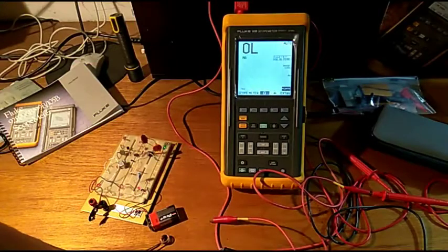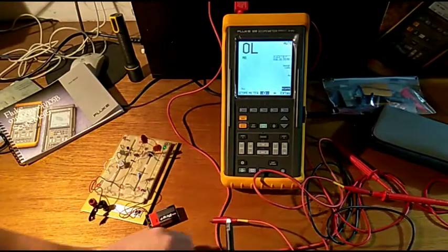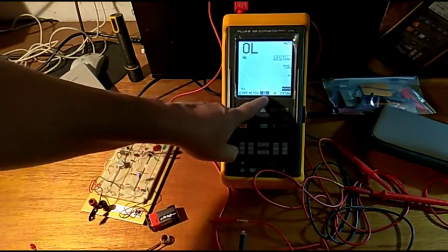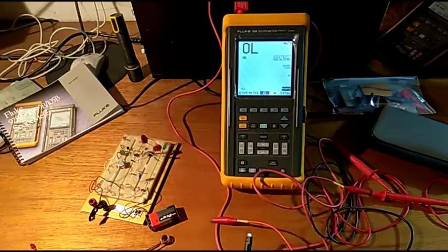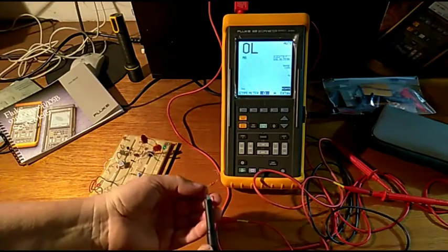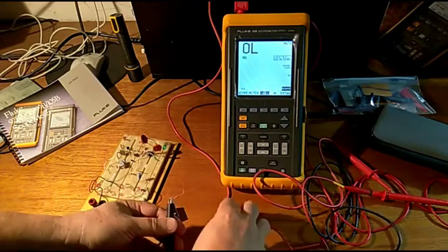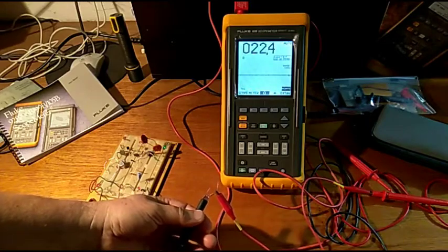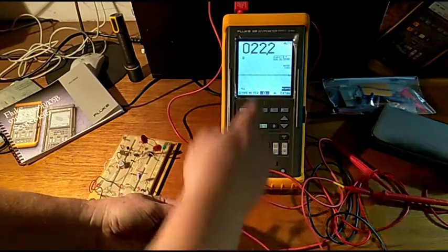Now we'll test the resistance meter. We're in ohm mode on the Fluke 92B. Let's pick up a resistor here. It's red red black, so that should be 22 times 10 to the zero, or 22 ohms. Let's see what it measures. Approximately 22.1 ohms. The resistance meter is working.